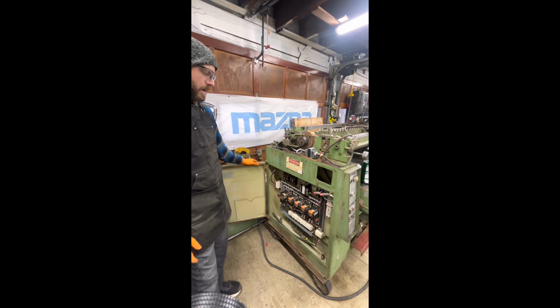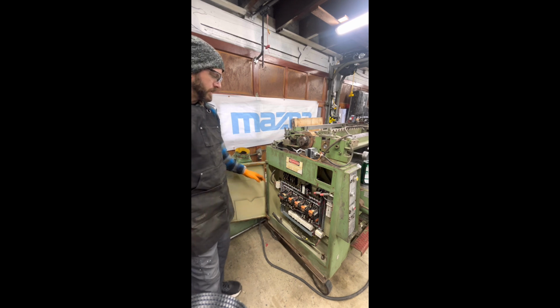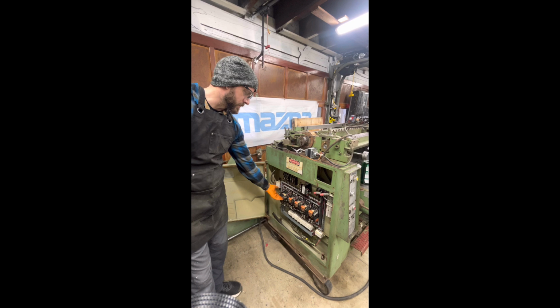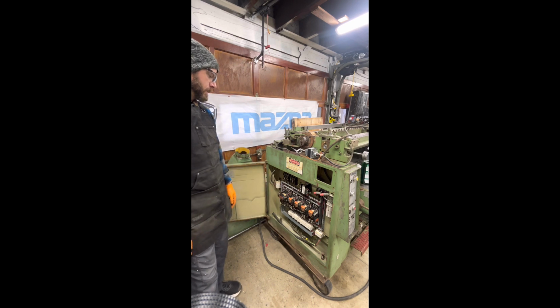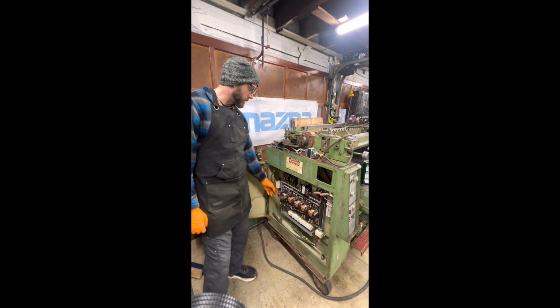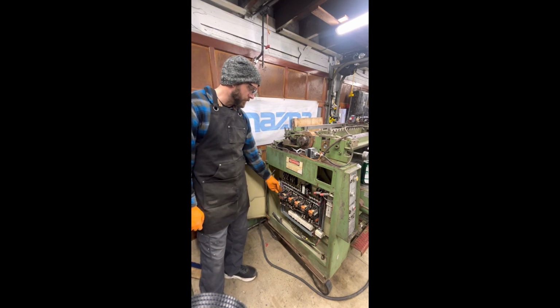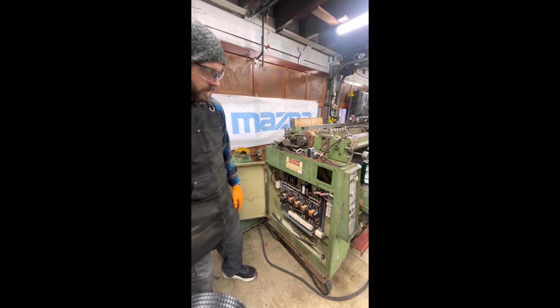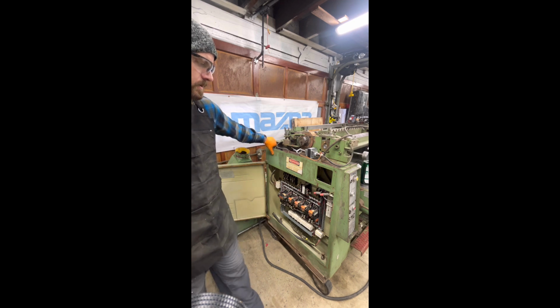So I vacuumed it all out, took contact cleaner and blew down all these motor starters down here, and cleaned everything up. A lot of these motor starters are pretty old, but on some of them it looks like maybe water was dripping in or starting to corrode in spots, some of the aluminum frames on them. But they're still working, the contacts look good in them.